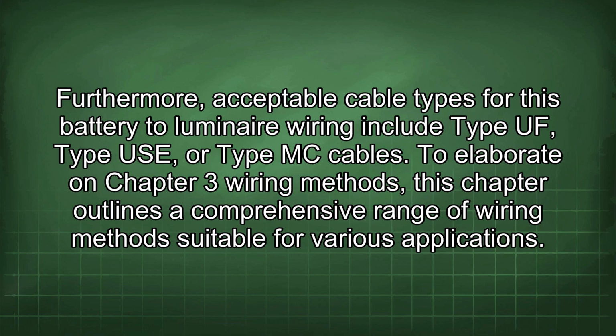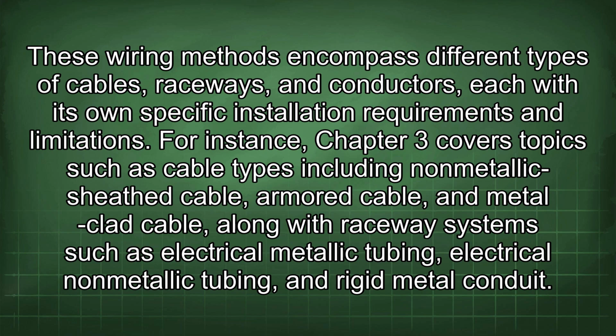To elaborate on Chapter 3 wiring methods, this chapter outlines a comprehensive range of wiring methods suitable for various applications. These wiring methods encompass different types of cables, raceways, and conductors, each with its own specific installation requirements and limitations. For instance, Chapter 3 covers topics such as cable types including non-metallic sheath cable, armored cable, and metal-clad cable, along with raceway systems such as electrical metallic tubing, electrical non-metallic tubing, and rigid metal conduit.